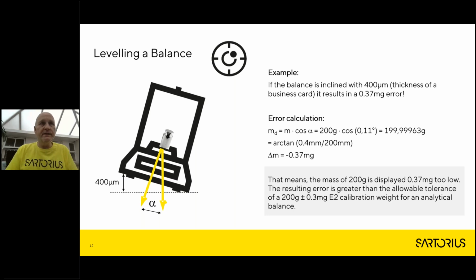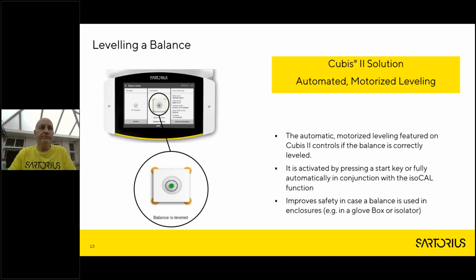So we want to level the balance before we use it. How do we do that? Well, in its simplest form, most balances will have a level bubble. Nowadays, we have electronic assisted leveling on the Cubis 2 balance, the balance detects when it is out of level. It informs you on the display, and then at the touch of a button, we have automatic motorized leveling, which will bring your balance back into level. Once you've leveled your balance, you should, of course, perform a calibration as well to make sure that the slope of the balance is correct. We can also use the balance in safety cabinets, and automatic leveling in a safety cabinet is particularly useful rather than having to stretch into the cabinet to level your balance.